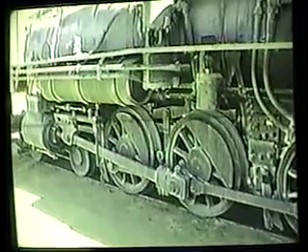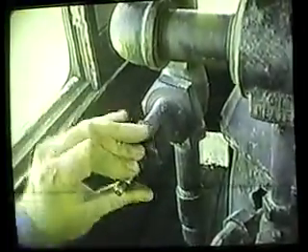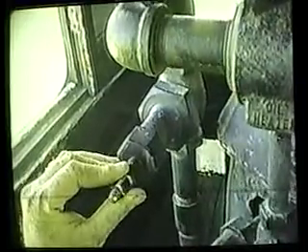You'd then open the fire door. Remove any carbon, fire brick, or other obstruction that would interfere with the flame traveling from the burner to the opposite end of the firebox at the flash wall. Next, you'd open the damper. Open your blower valve, create a draft through the firebox.